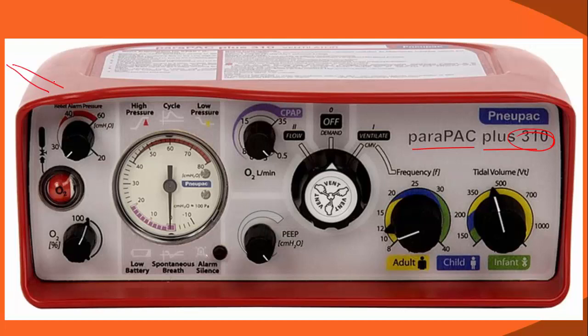Your oxygen tank would connect in the rear to this device, and we have this piece here, a little rotating ball. It would turn green when high flow O2 is connected to show you that the O2 tank is providing pressure. It doesn't tell you how much pressure is available in the tank though, so you do need to be aware of that. Down here, this setting gives us our FiO2. Most of them have a setting that's 100, some go to 0, others go only to 50, and some means in between. So we're setting the percentage of oxygen the patient gets.